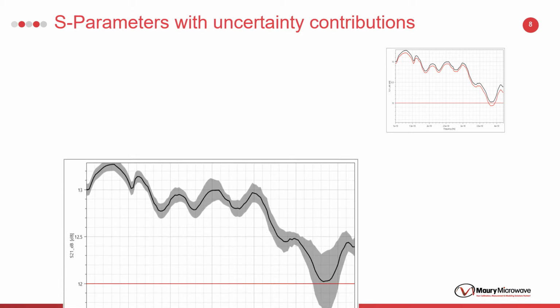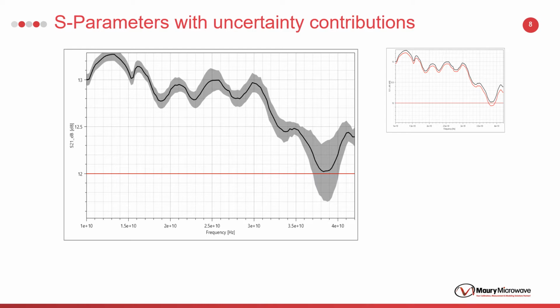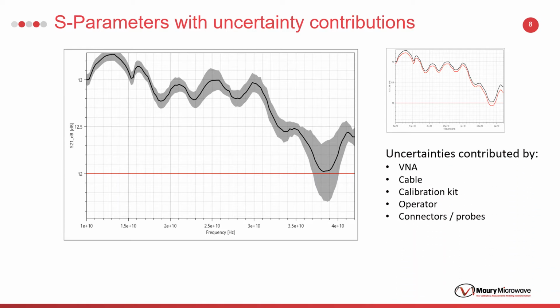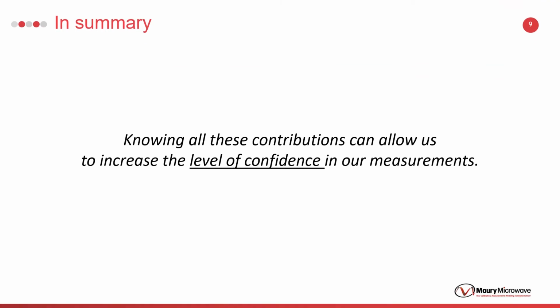After considering these error sources and adding them to the measurement, we can visualize the uncertainty contribution to the S-parameter measurements. Depending on the system and amount of errors, uncertainty added to measurement data may vary considerably and cause failures. After measuring our sample device by considering uncertainties of the measurement setup, we observed that some of the estimated measurements fell below the spec and the device failed. In summary, knowing all these uncertainty contributions can allow us to increase the level of confidence in our measurements. This valuable information can be transformed into improved measurement performance and product quality.